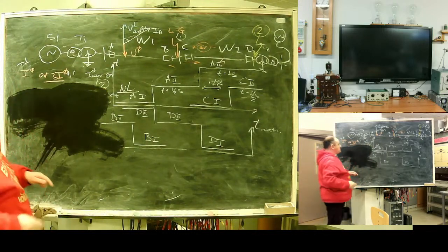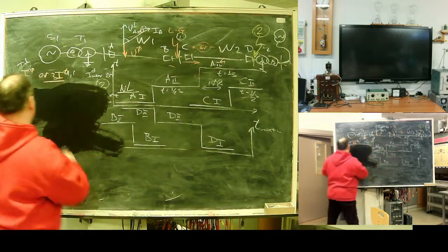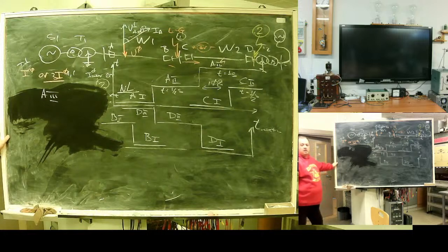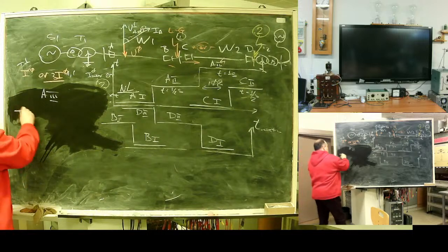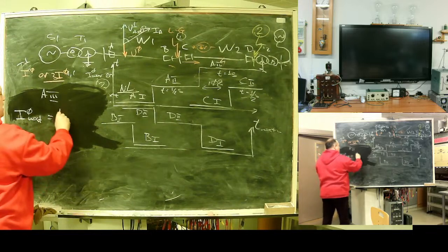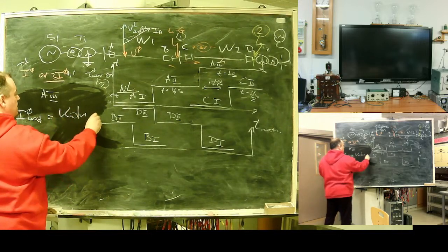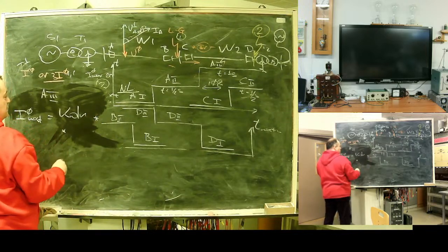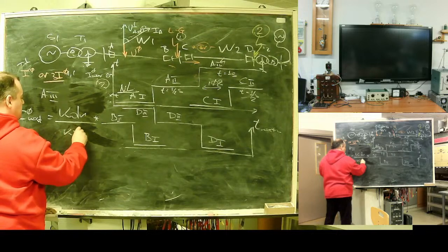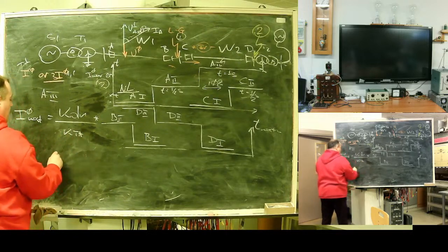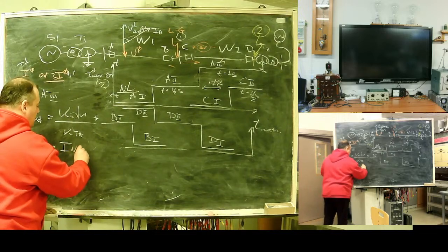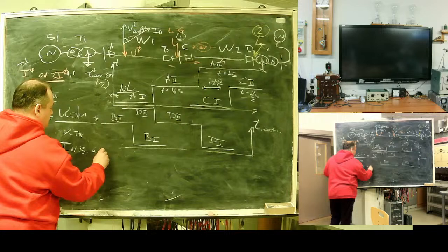So for last zones, like A3, driving factor is non-balanced. Here, trip current should be safety factor divided by transformer and multiplied by non-balanced current max.